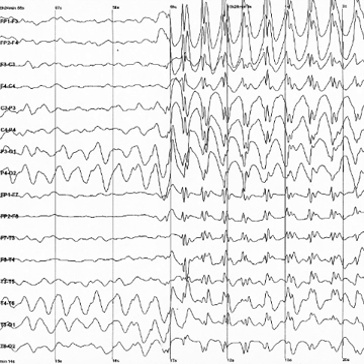In analog EEG, the signal is then filtered, and the EEG signal is output as the deflection of pens as paper passes underneath. Most EEG systems these days, however, are digital, and the amplified signal is digitized via an analog-to-digital converter, after being passed through an anti-aliasing filter.